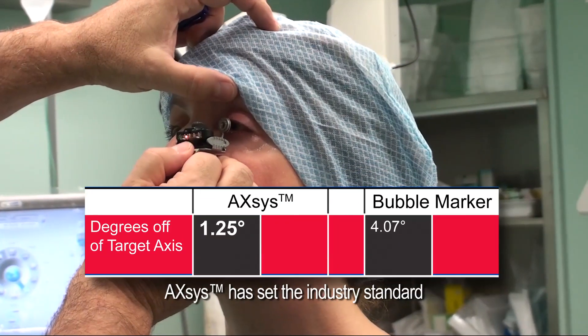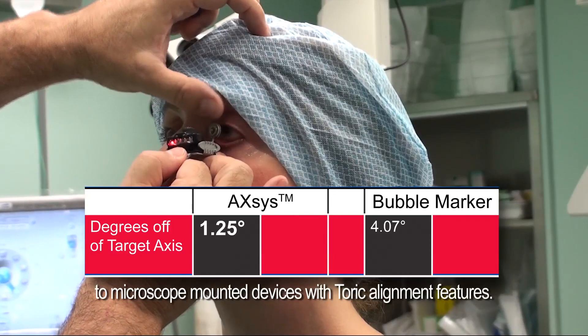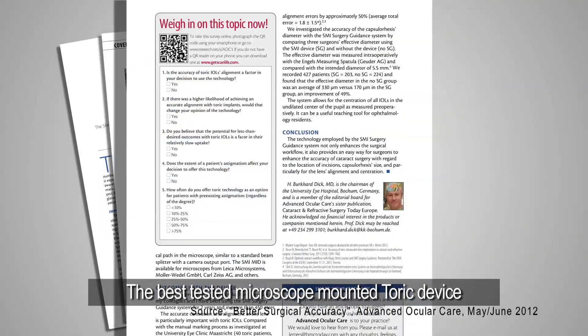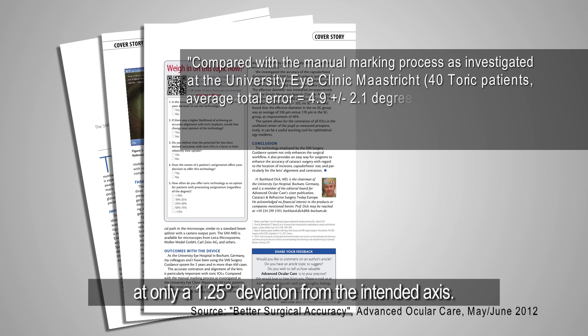AXsys™ has set the industry standard for accurate toric lens alignment, as the clinical study results were also compared to microscope-mounted devices with toric alignment features. The best-tested microscope-mounted toric device showed an average alignment error of 1.8 degrees, while AXsys™ tested 31% more accurately, at only a 1.25-degree deviation from the intended axis.